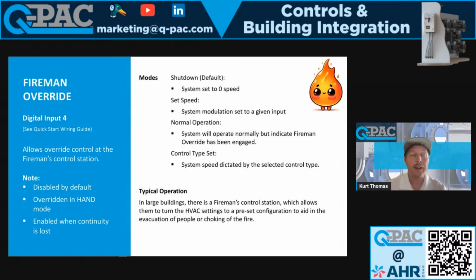So if our fans are feeding, say, a stairwell, and there's a fire, then you want to make sure that the fans are running and moving as much air in that stairwell as possible. You want the folks that are exiting the building to be able to breathe and to continue to have oxygen. If our fans are feeding some of the top floors that may be on fire, you probably want our fans to shut off so that you can help choke out that fire so you don't continue to feed it with fresh oxygen. So these are all preset settings.